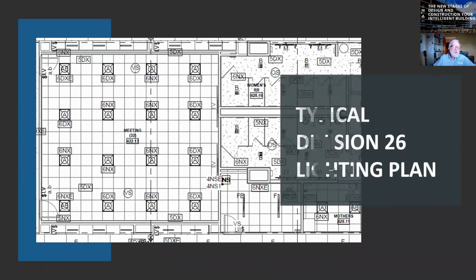So here's a typical Division 26 lighting plan, or typical as can be. This particular one is POE. You'll notice we have light fixtures here—these 2x2s are light fixtures, type A, and E indicates it's an emergency fixture.